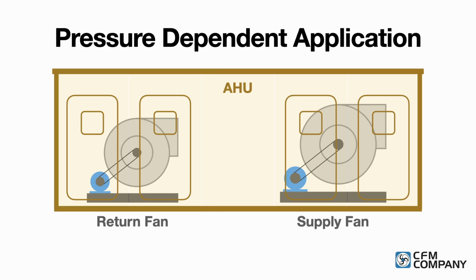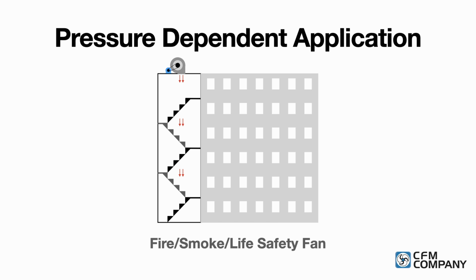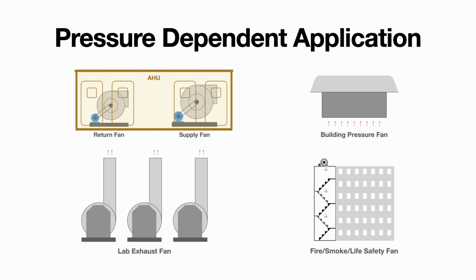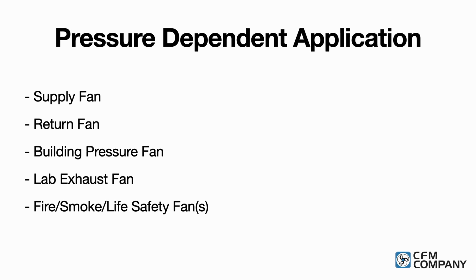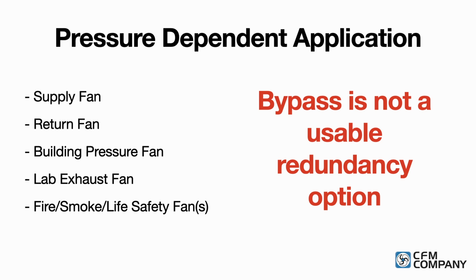However, there are customers who know that their equipment cannot run across the line at 100% speed in bypass. Typically, this applies to equipment that must maintain a pressure set point, such as a supply fan, a return fan, a building pressure fan, a lab exhaust fan, or a fan used for fire smoke and life safety. For these equipment types, use of bypass will overpressurize the system and could cause serious life safety issues for the building's fire smoke applications. For pressure-dependent applications, bypass is not a usable redundancy option.